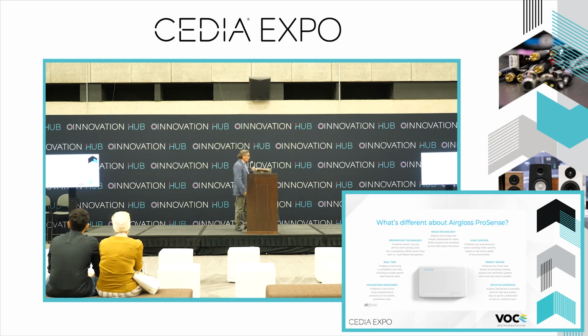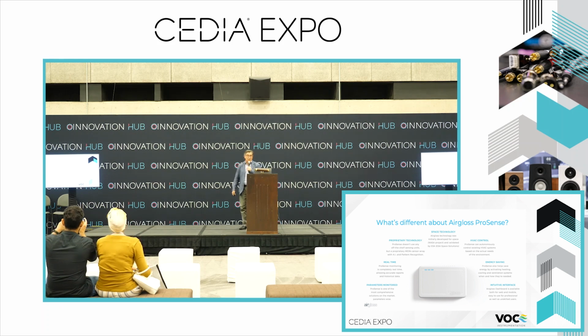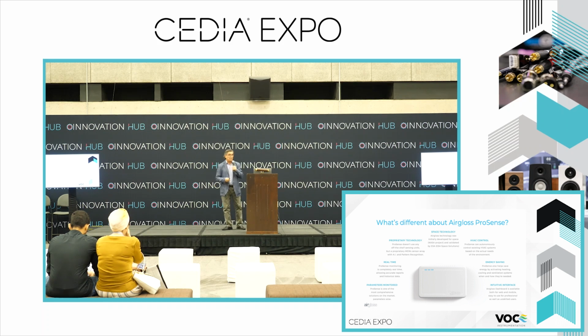So what's different about Airgloss? Well, there's a couple of things I think that we need to know. Obviously, we talked about space technology. I think that's a good legacy for the product and the device itself. I mentioned the proprietary technology. We use a sensor array, a MEMS sensor array, using artificial intelligence and pattern recognition. The device monitors real time, 24/7. It's for those who want to use this with an HVAC system. It's connectable via the cloud, via BACnet protocol, via Modbus. So it's very versatile in how it can connect and provide the information.